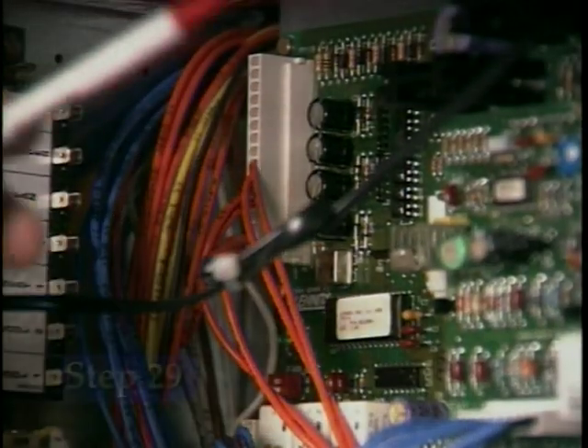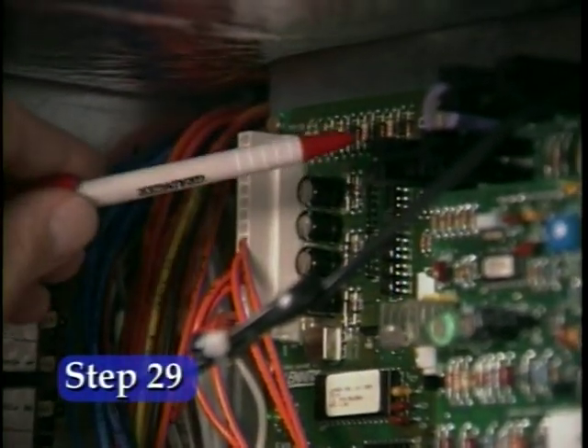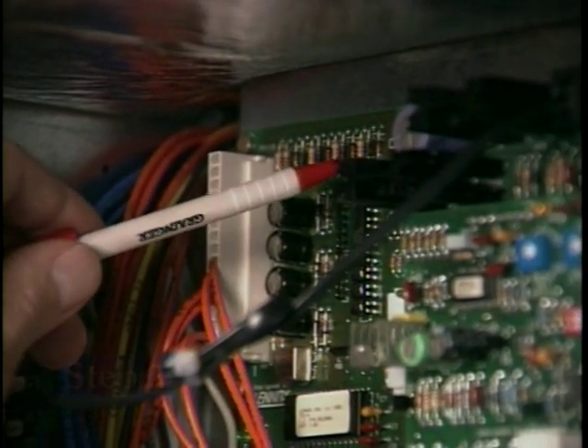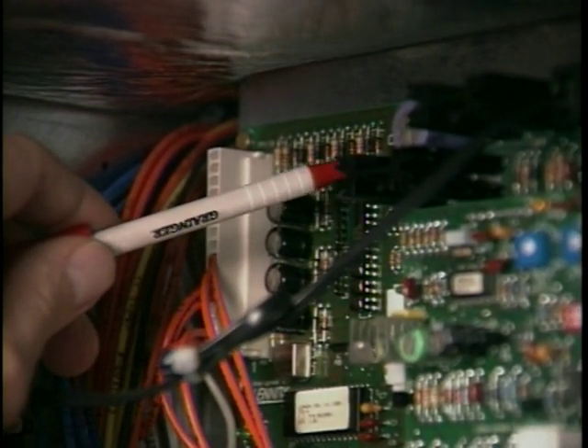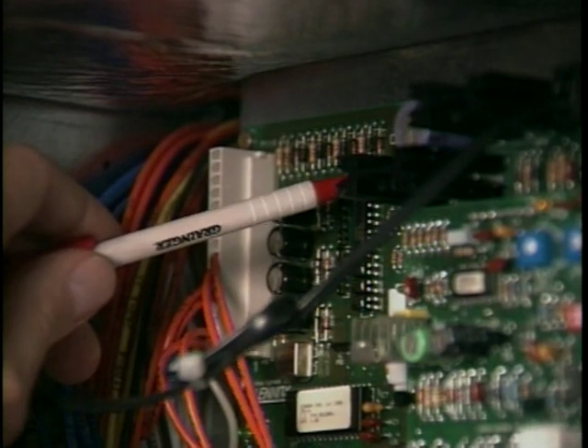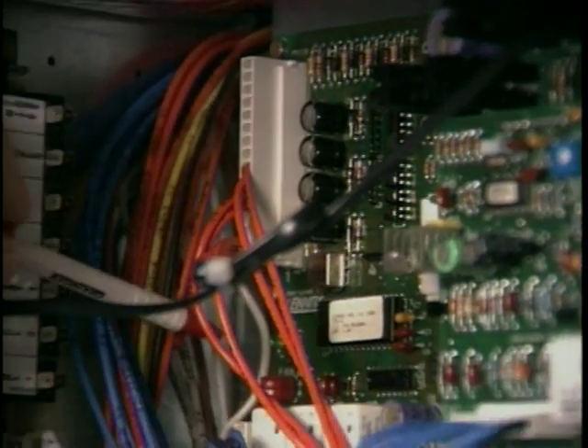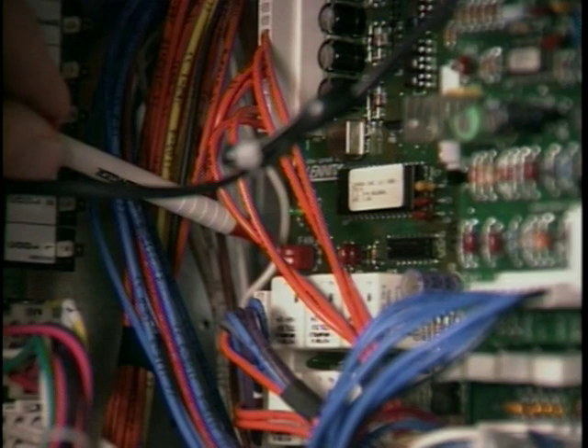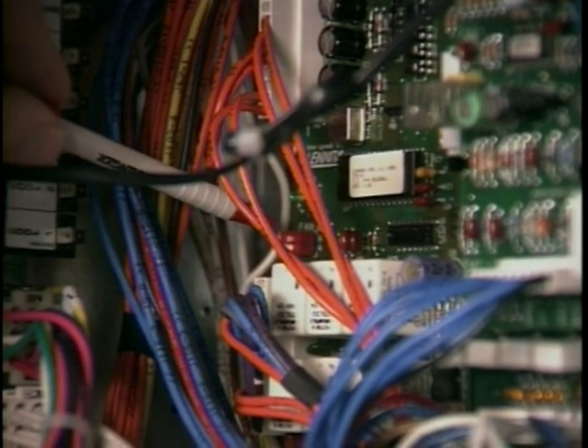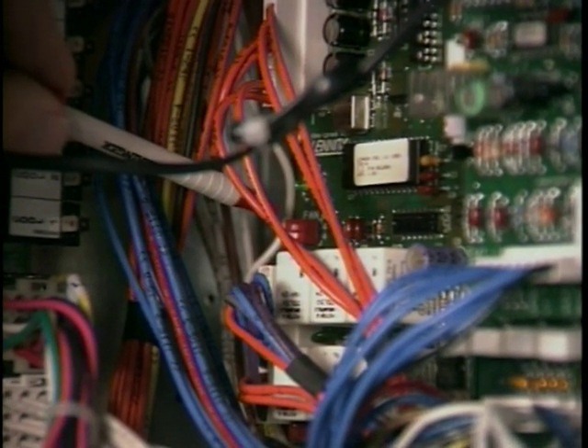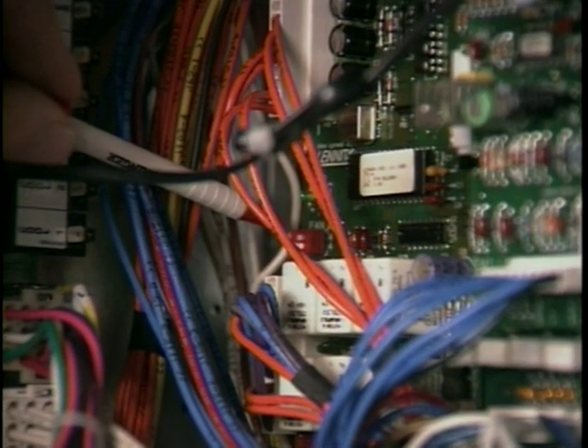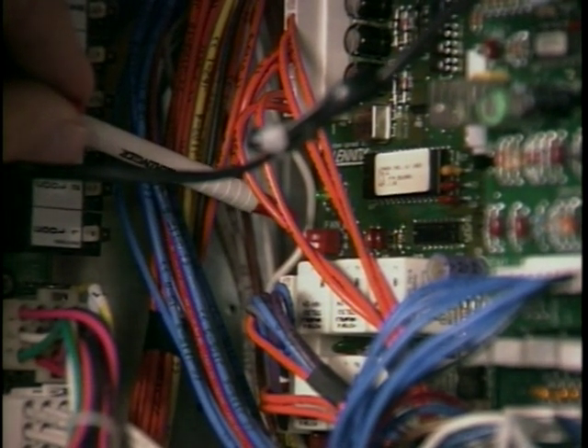To the left of the A55 board is the A59 board or the A61 board. The A59 board is used for gas or cooling-only units. The A61 board is used for heat pumps. Either board has a 2-position dip switch, SW1. This switch configures the system to the correct number of fans and compressors. Check that the settings agree with the unit configuration.